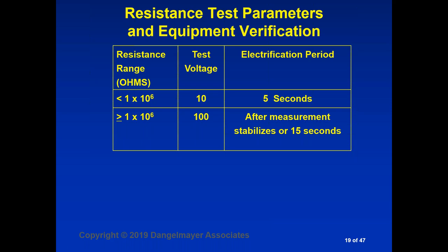If the resistance range is more than 10 to the sixth ohms, you're going to use a test voltage of 100 volts. Now, your test instrument may have a manual switch to switch between the two, or it may do it automatically, depends on the test instrument. But if you're going to make measurements at these higher resistances, basically it's going to take longer for the measurement to stabilize. So in this case, we wait until you can see the measurement has stabilized, or 15 seconds, whichever is less.